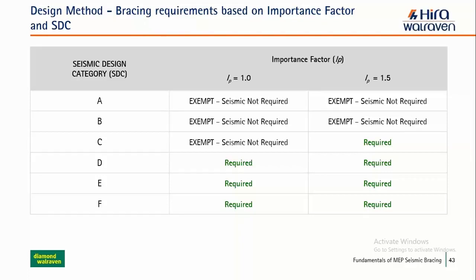If seismic design category is C, seismic treatment is exempt for equipment with importance factor 1.0 (non-life safety), and required only for life safety (1.5). If seismic design category is D, it's required for both 1.0 and 1.5. The same follows for E and F, but mostly we're not in regions that severe. D is usually the worst case major concern.